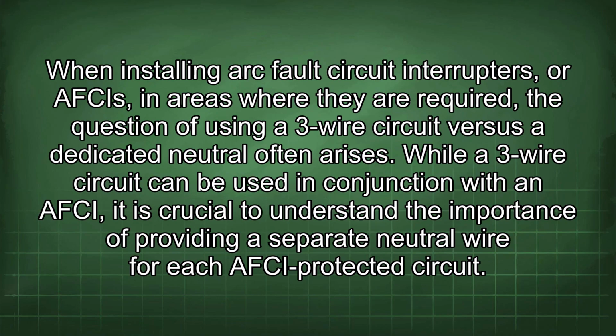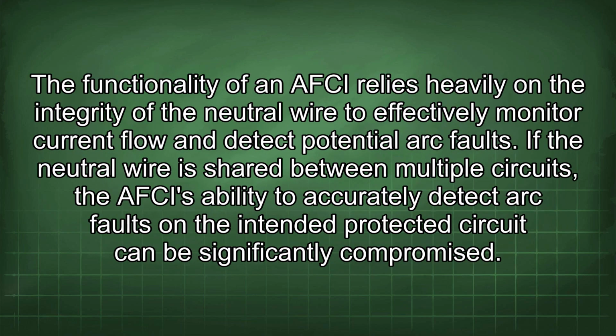When installing arc fault circuit interrupters, or AFCIs, in areas where they are required, the question of using a 3-wire circuit versus a dedicated neutral often arises. While a 3-wire circuit can be used in conjunction with an AFCI, it is crucial to understand the importance of providing a separate neutral wire for each AFCI protected circuit. The functionality of an AFCI relies heavily on the integrity of the neutral wire to effectively monitor current flow and detect potential arc faults. If the neutral wire is shared between multiple circuits, the AFCI's ability to accurately detect arc faults on the intended protected circuit can be significantly compromised.